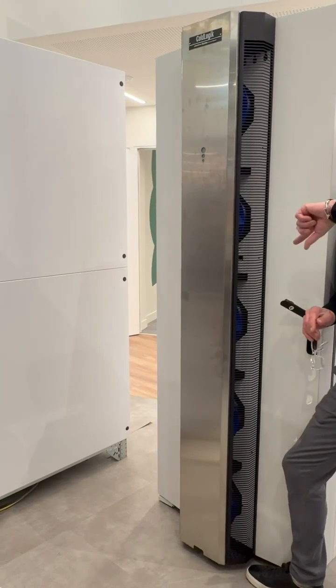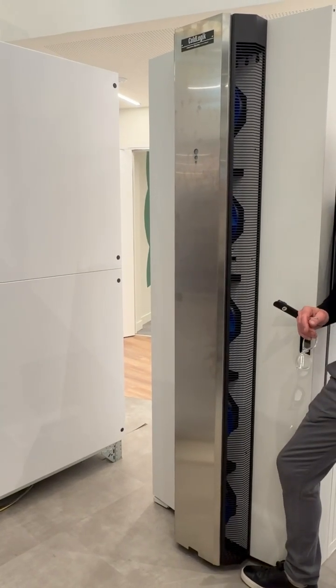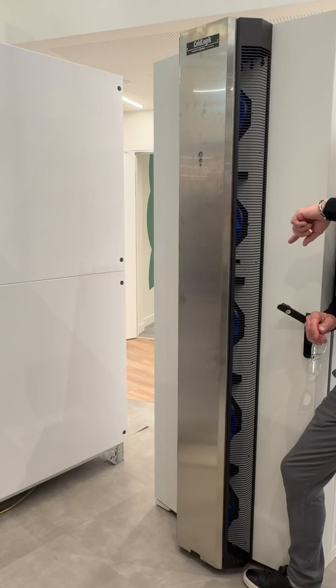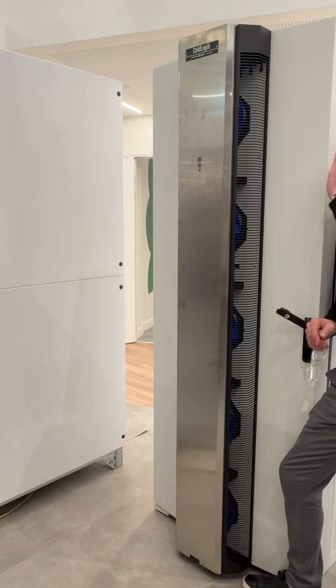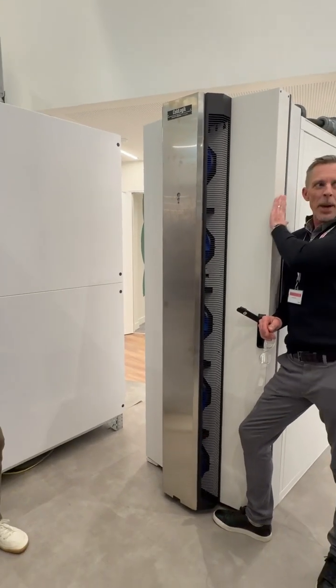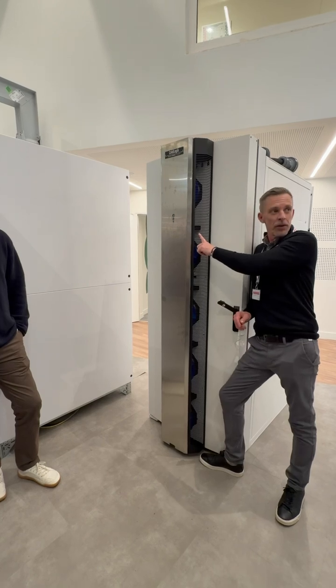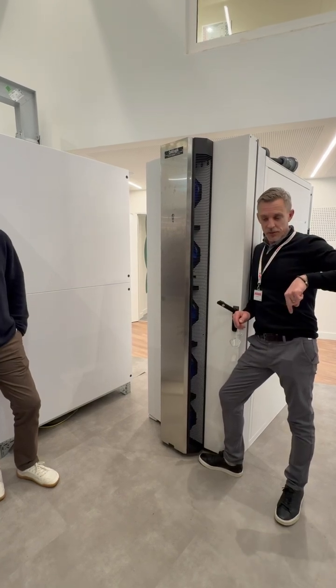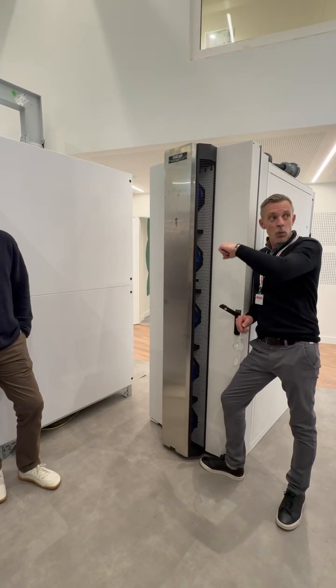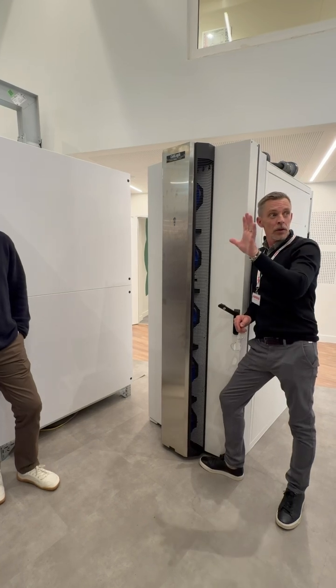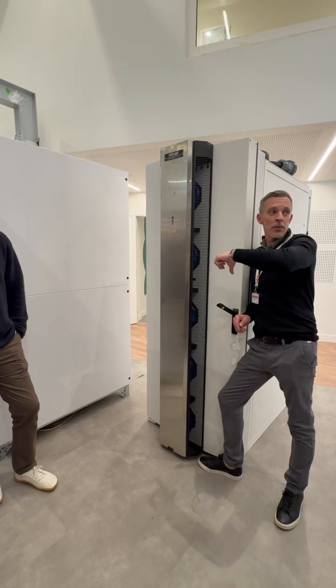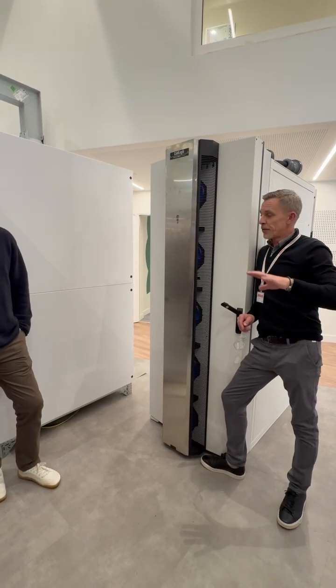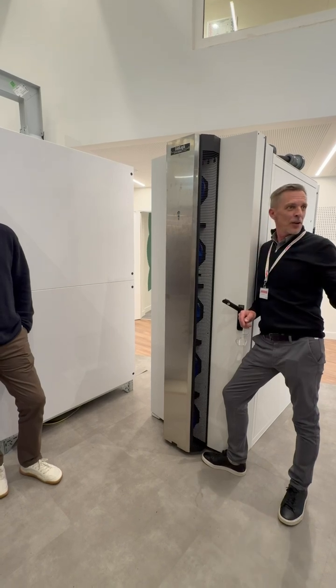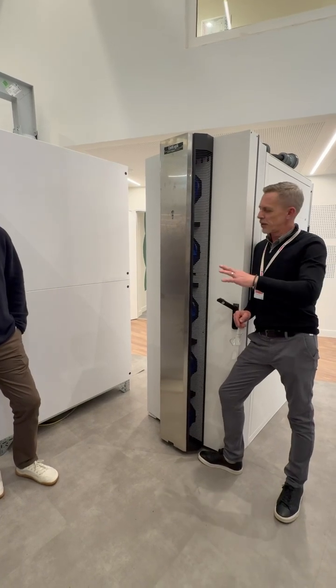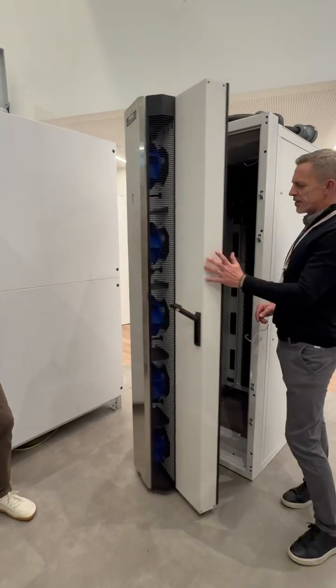By us doing this, ultimately it works in conjunction with each individual rear door as it goes along. So what that means is if I lose, for any reason whatsoever, power to this cabinet, this door fails, my rear door next to it or the rear door to the other side of it will pick up the heat load of the room and give the ultimate ambient temperature to the whole facility. So it's an N+N or an N+1 solution, depending on how you do it. So that's temperatures.